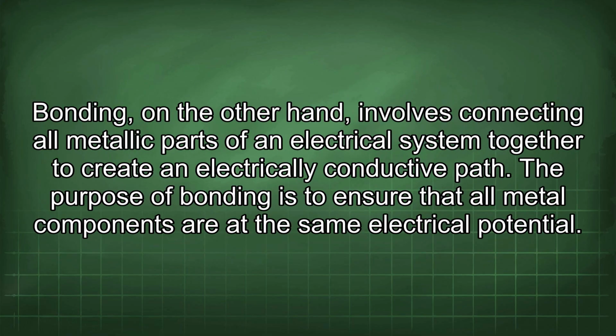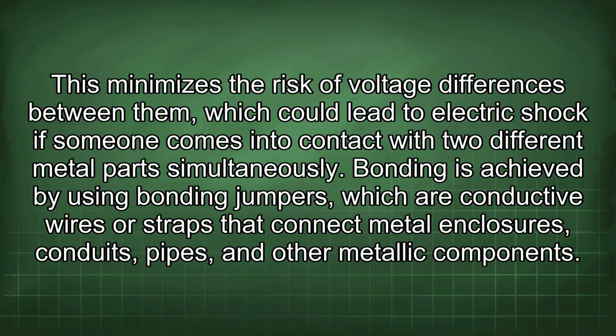Bonding, on the other hand, involves connecting all metallic parts of an electrical system together to create an electrically conductive path. The purpose of bonding is to ensure that all metal components are at the same electrical potential. This minimizes the risk of voltage differences between them, which could lead to electric shock if someone comes into contact with two different metal parts simultaneously. Bonding is achieved by using bonding jumpers, which are conductive wires or straps that connect metal enclosures, conduits, pipes, and other metallic components.